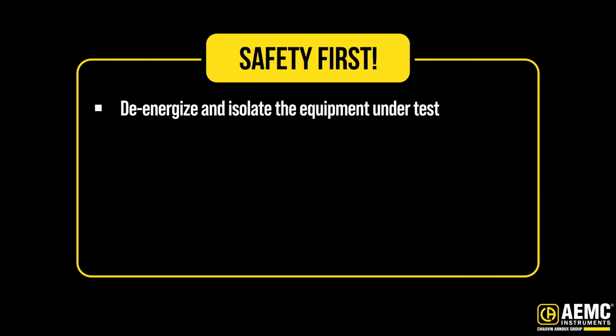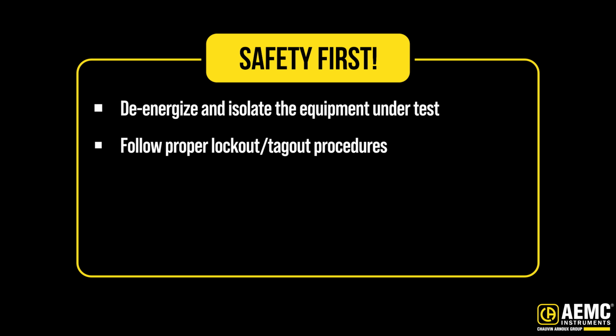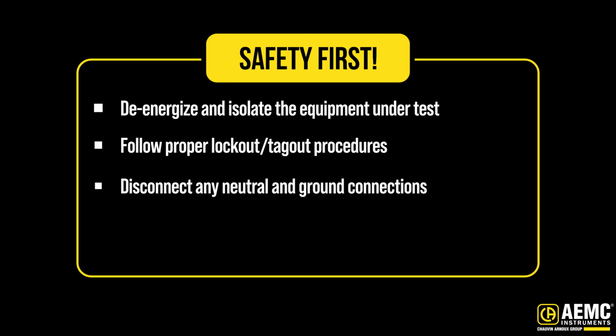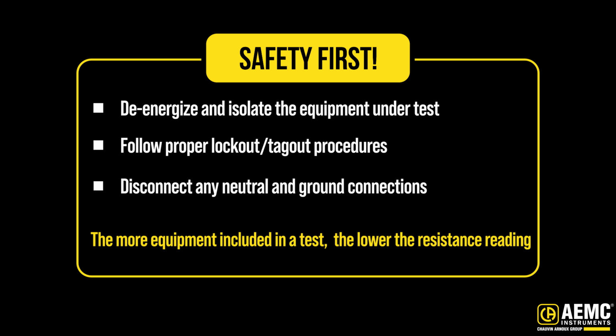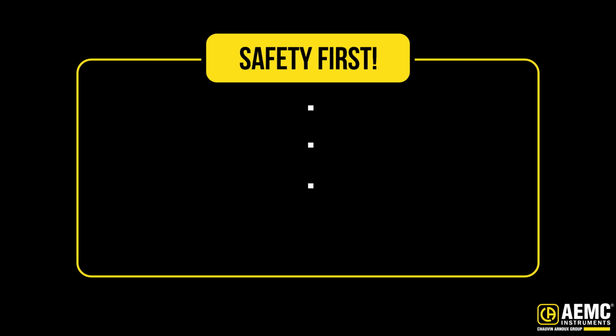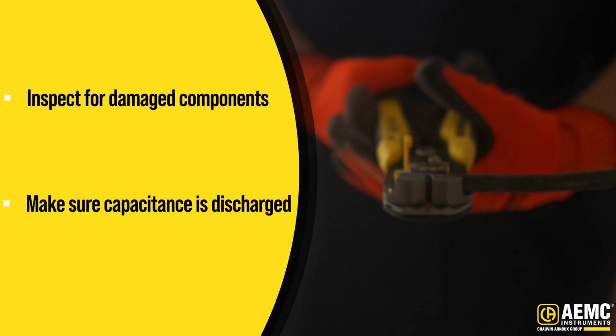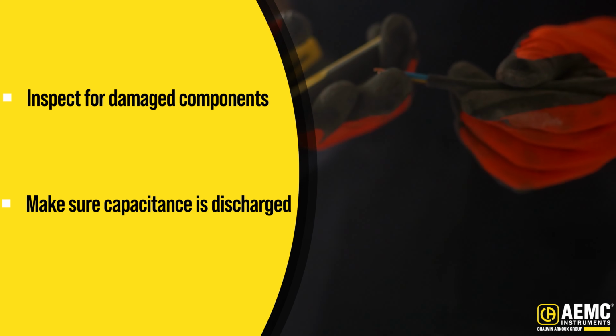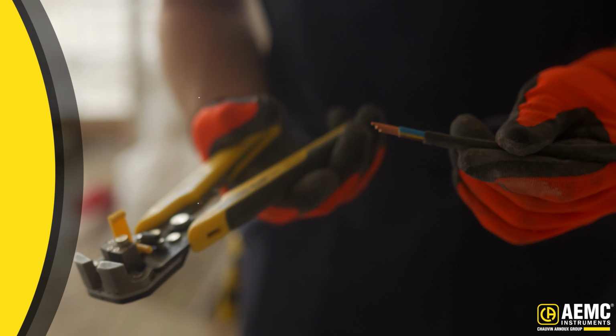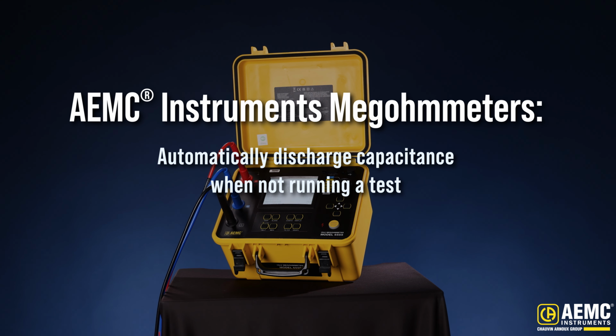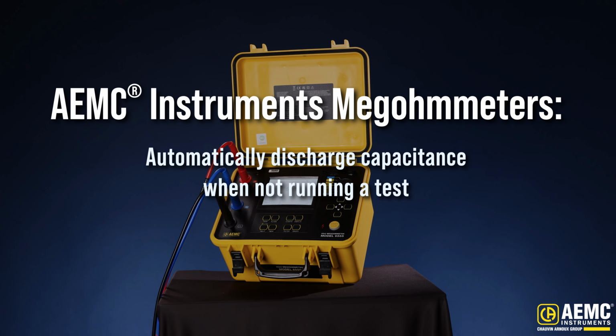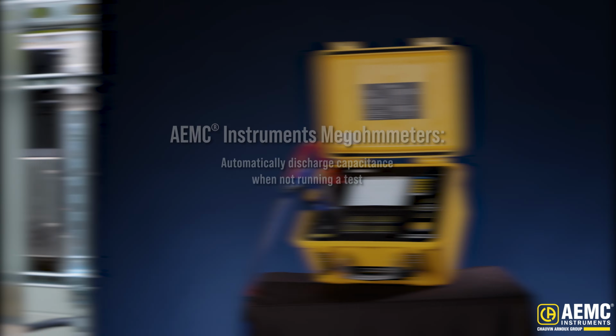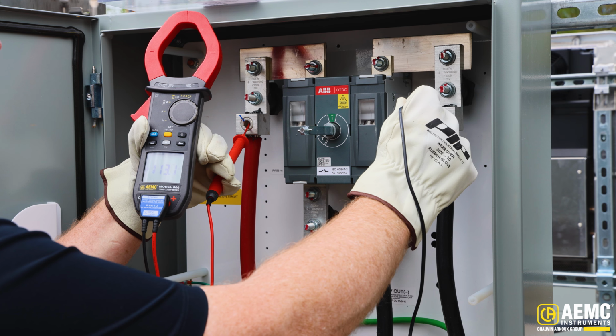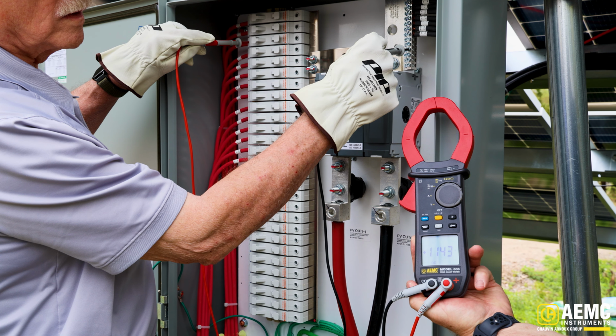De-energize and isolate the equipment under test. Follow proper lockout and tagout procedures. Disconnect any neutral and ground connections. In general, the more equipment included in a test, the lower the resistance reading. Inspect for damaged components and make sure capacitance is fully discharged before and after testing. Note that AEMC Instruments Megohmmeters automatically discharge capacitance when not running a test. Finally, check current leakage at switches and other connections.